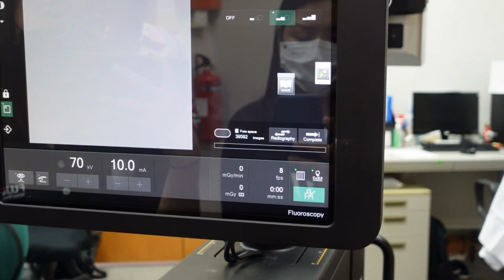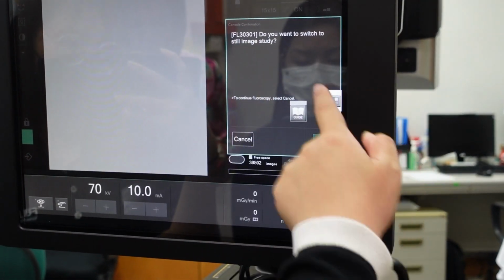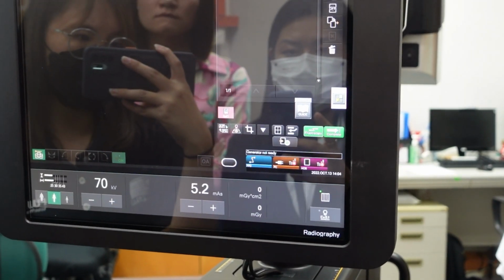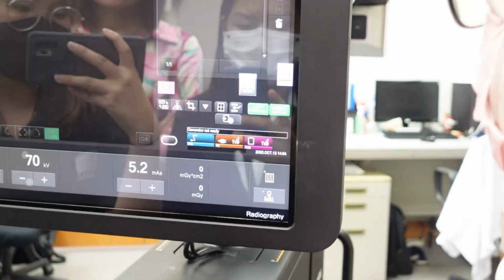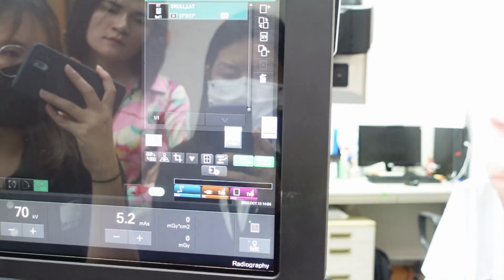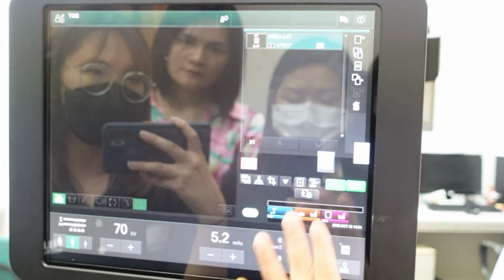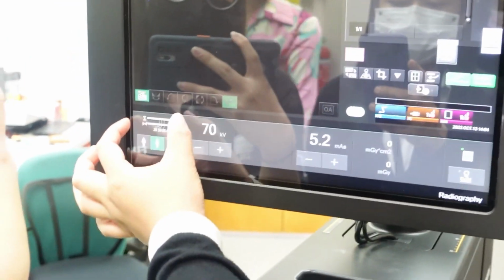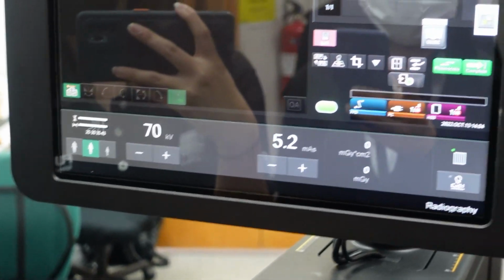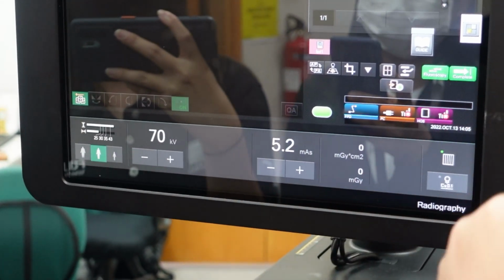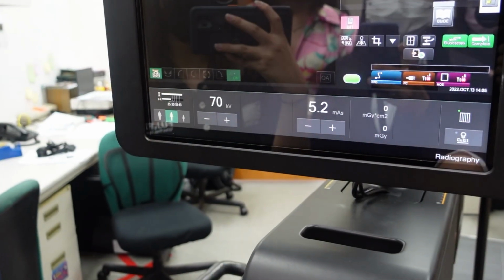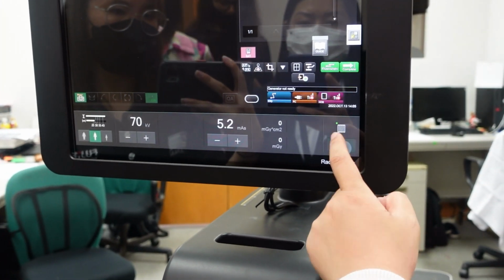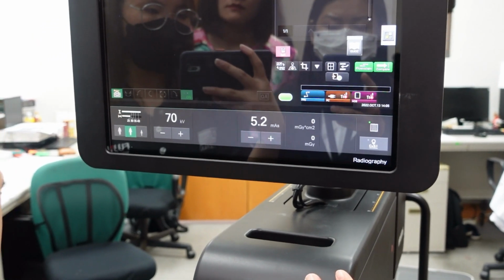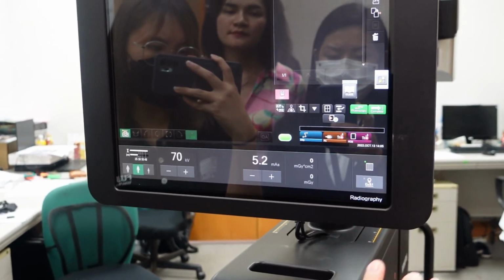Now, if you want to go to radiography mode, same patient, click this and this message will come up. Click OK and you hear that, meaning it's being switched. Wait until this is ready. There's the menu and this is ready. You're good to go. The rest is the same as your console advanced. Now in radiography mode you will see this. This is the size of your collimation. So this is the size of a collimation, and you have the so-called body habitus, exposure, the mAs. And this is where you activate or deactivate the additional 0.1 copper filter. The rest is the same as your console advanced. There's nothing else.